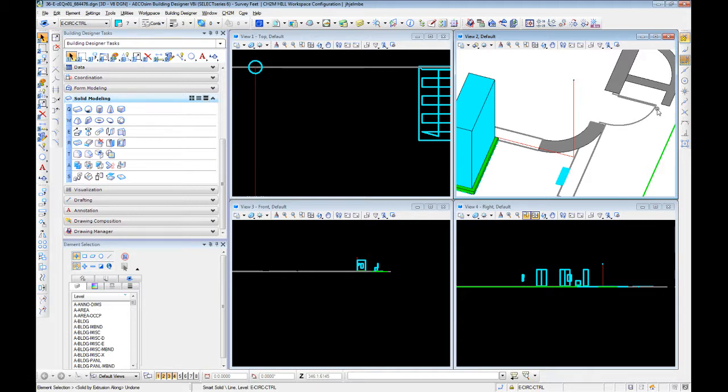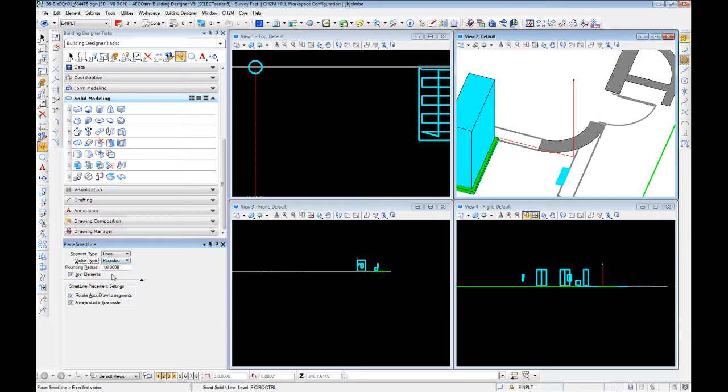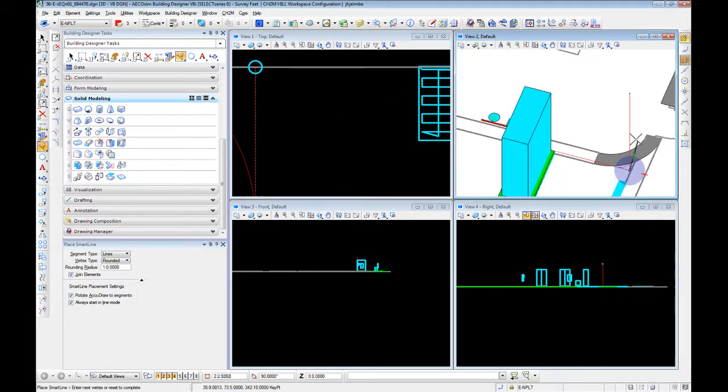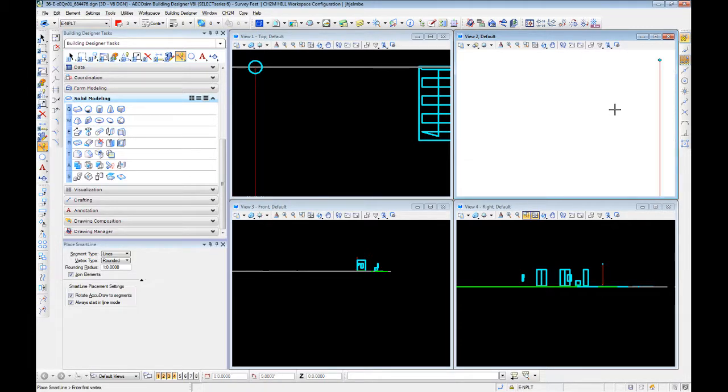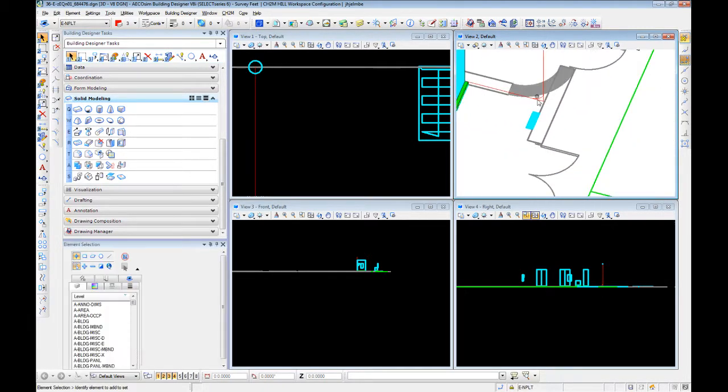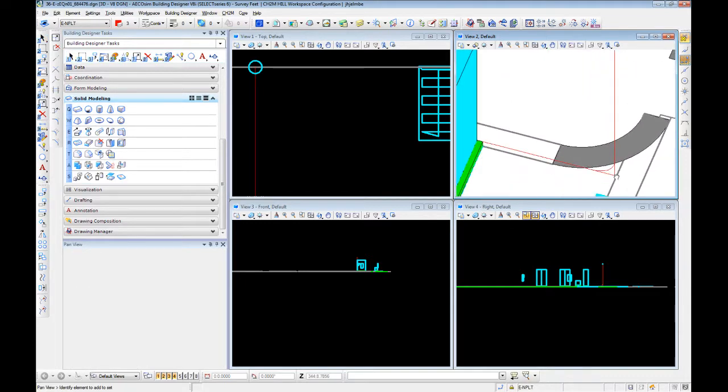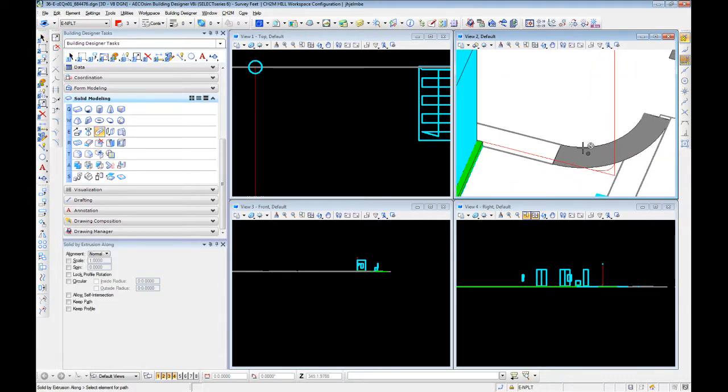Let's undo and go back. Using alt and left click, let's switch back to the no plot layer and go back into our smart line. What we can do is change our vertex type to rounded and set a radius. Let's say it's a 12 inch or one foot radius on that lower bend. Now you have something that looks more akin to how we would actually run conduit.